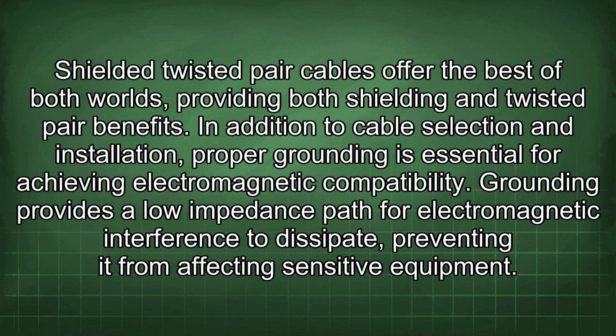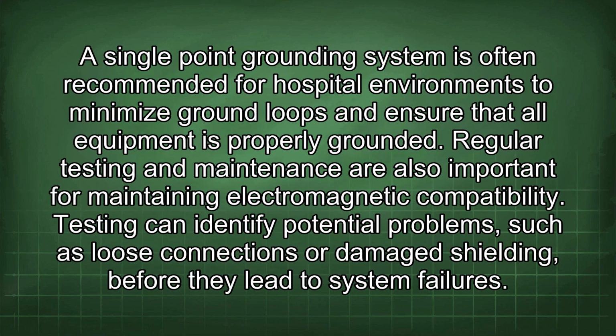In addition to cable selection and installation, proper grounding is essential for achieving electromagnetic compatibility. Grounding provides a low impedance path for electromagnetic interference to dissipate, preventing it from affecting sensitive equipment. A single-point grounding system is often recommended for hospital environments to minimize ground loops and ensure that all equipment is properly grounded. Regular testing and maintenance are also important for maintaining electromagnetic compatibility.